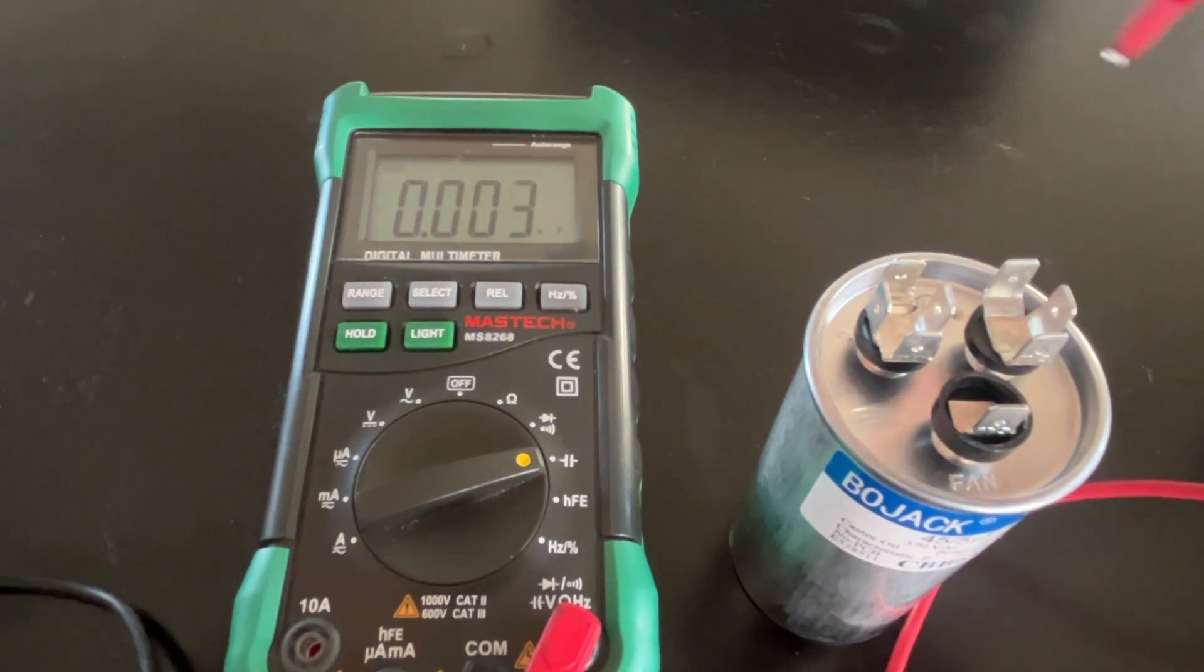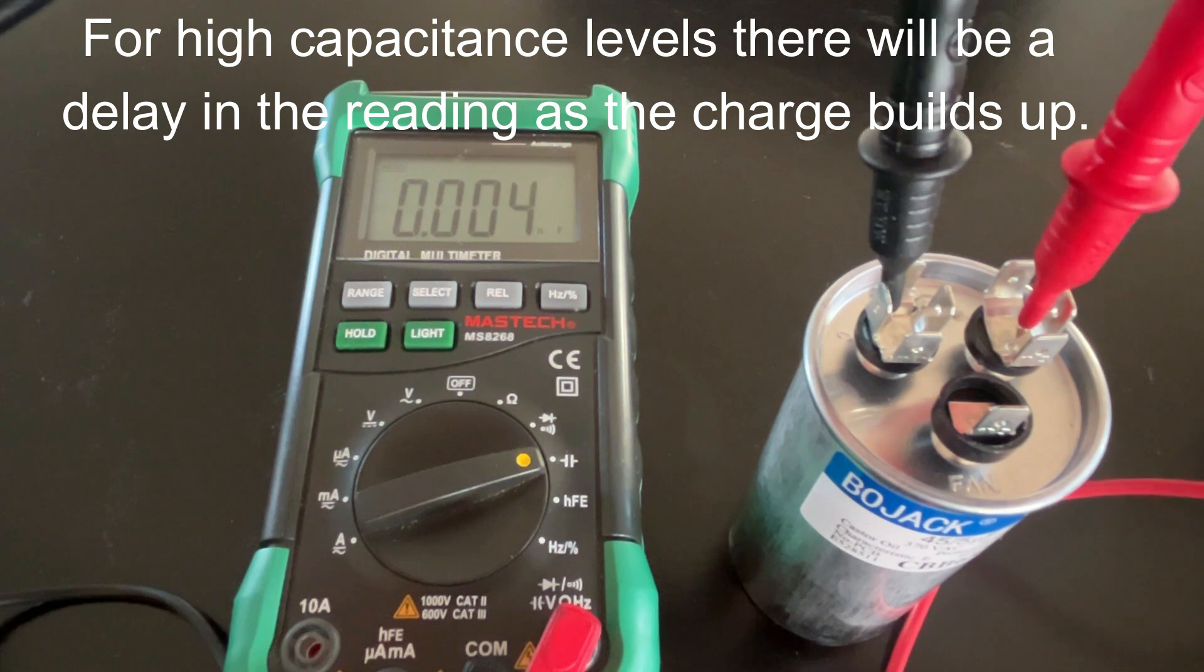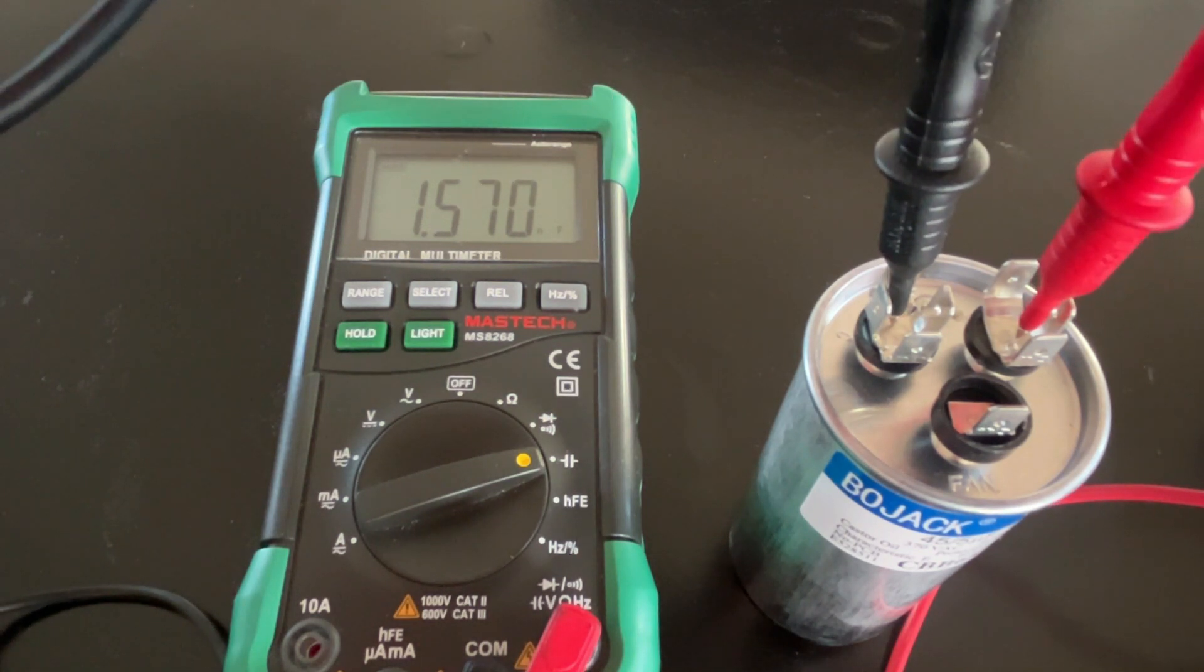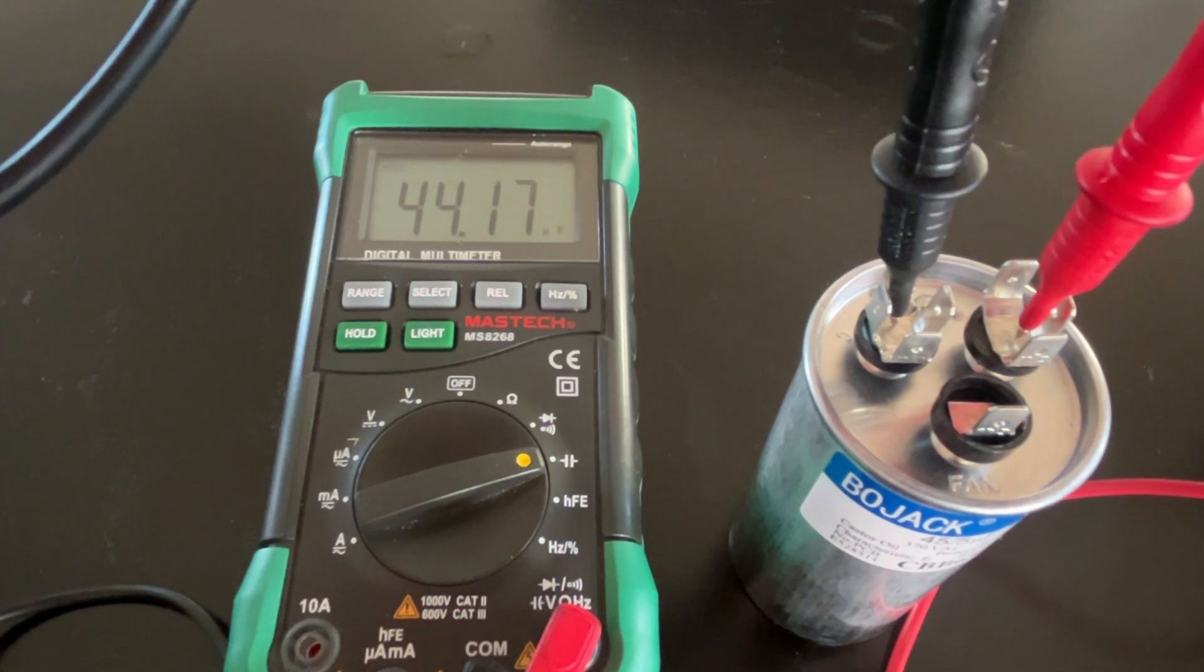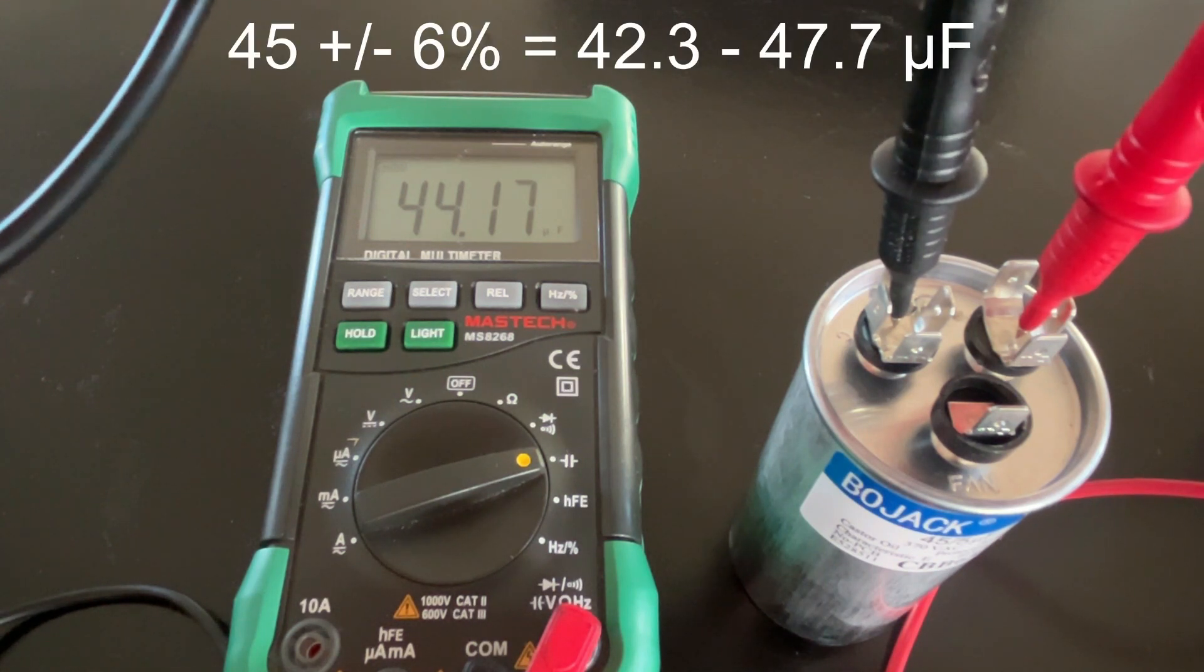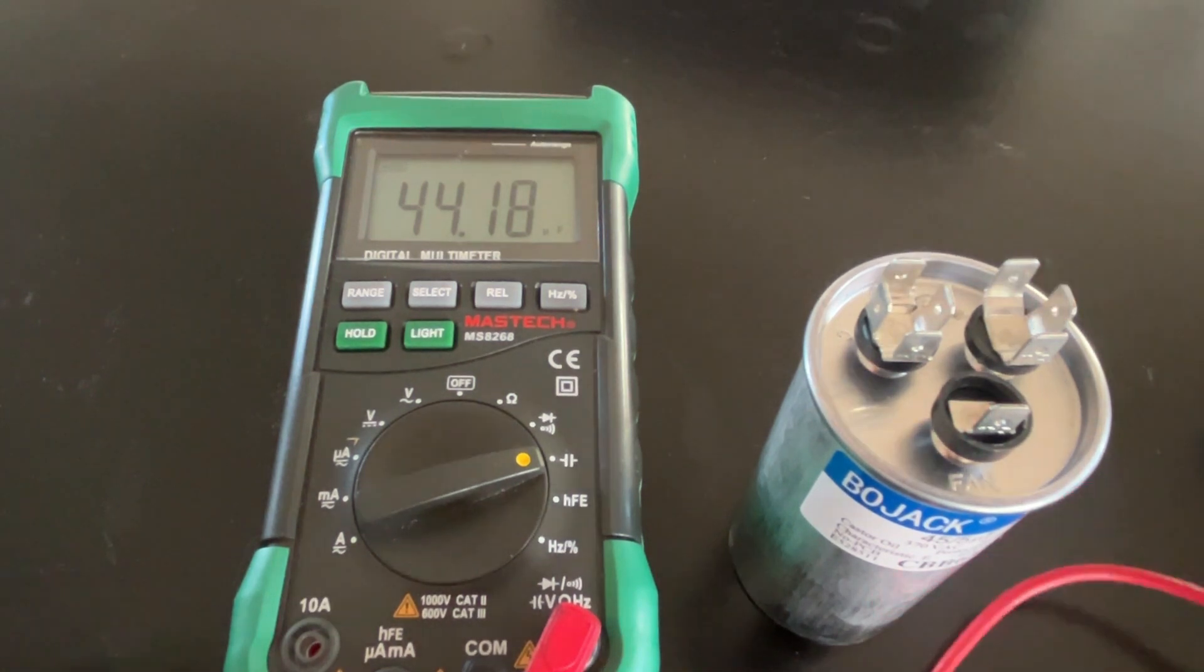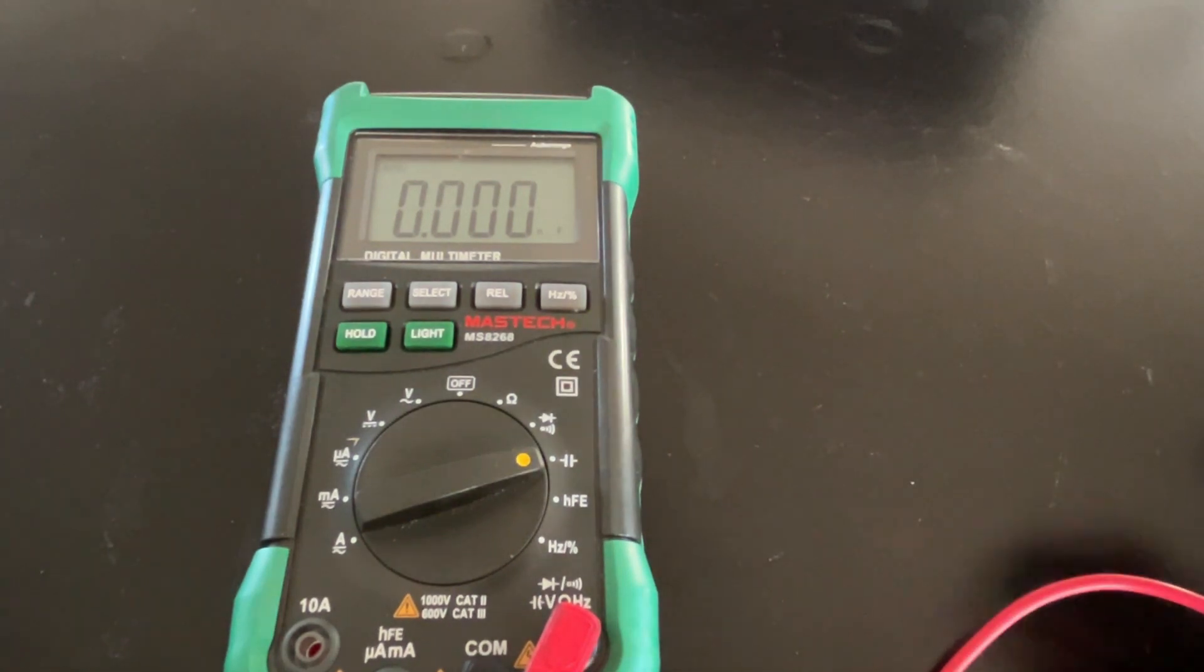All right, now let's check the compressor side of the capacitor. 44.17—so that is within six percent of 45, so this capacitor is good.